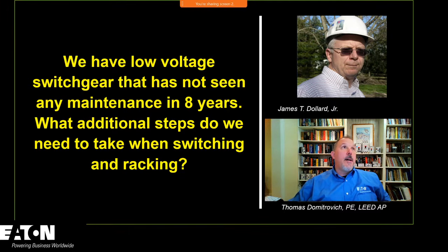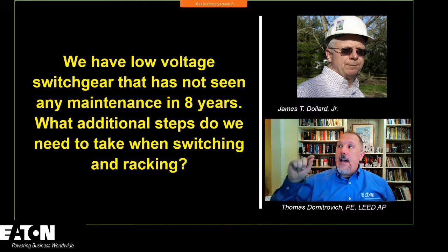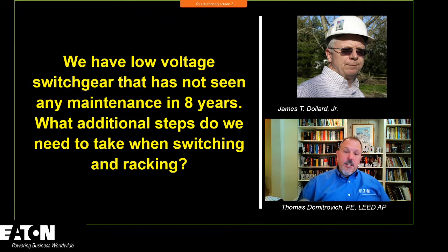All right. So this one here, we didn't hit this: maintenance. This is talking about maintaining your electrical equipment periodically. Now, this talks about low voltage switchgear that hasn't seen maintenance in 8 years. You have to take into consideration what the manufacturer recommends from a maintenance perspective. How often are you supposed to do maintenance, and things of that nature?